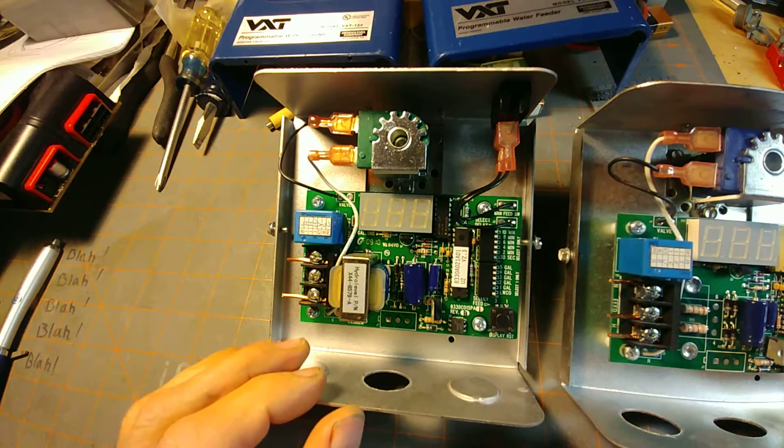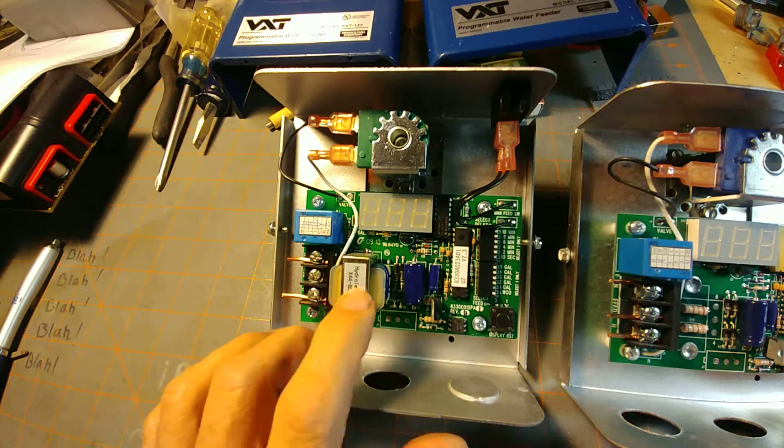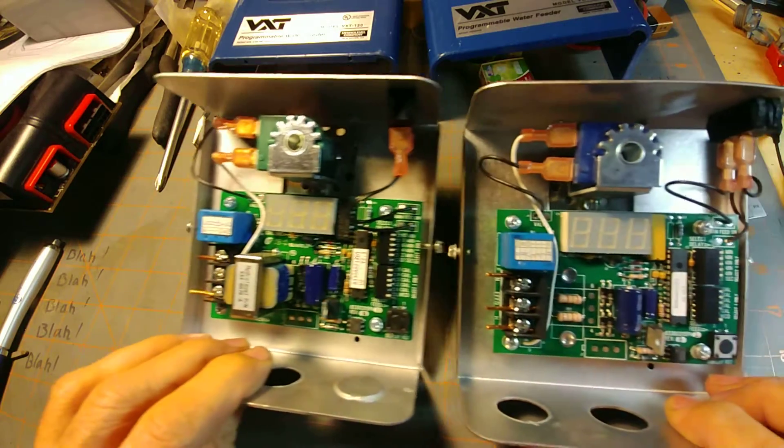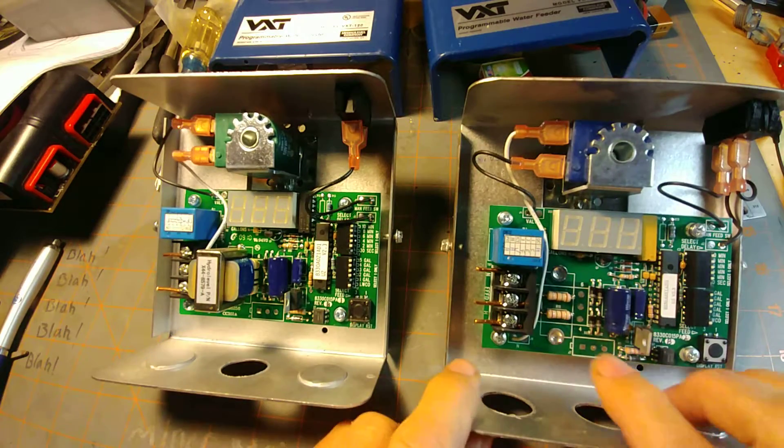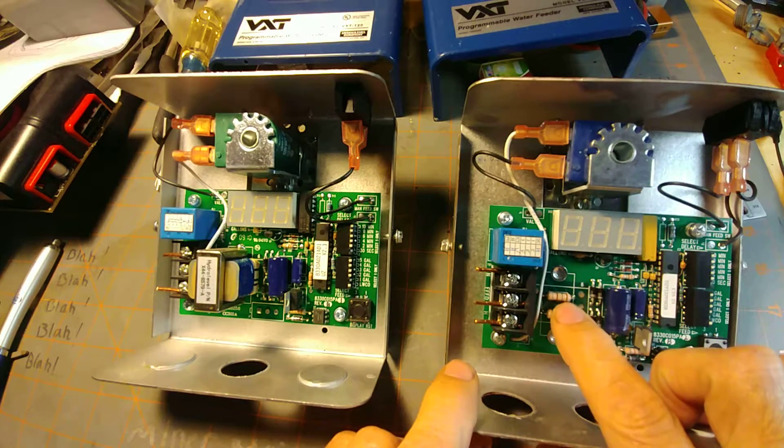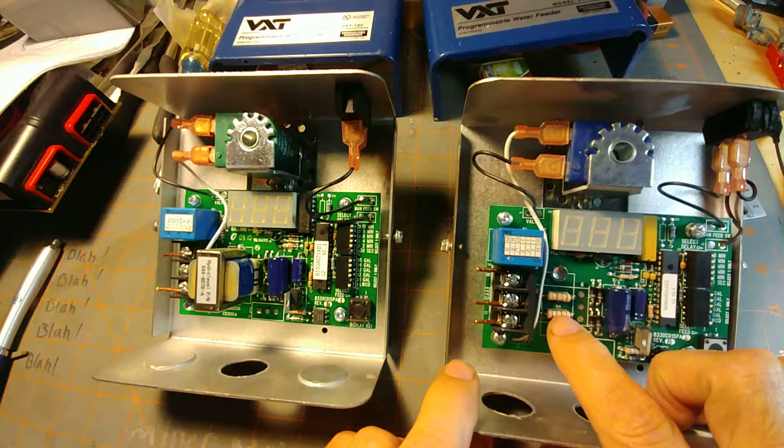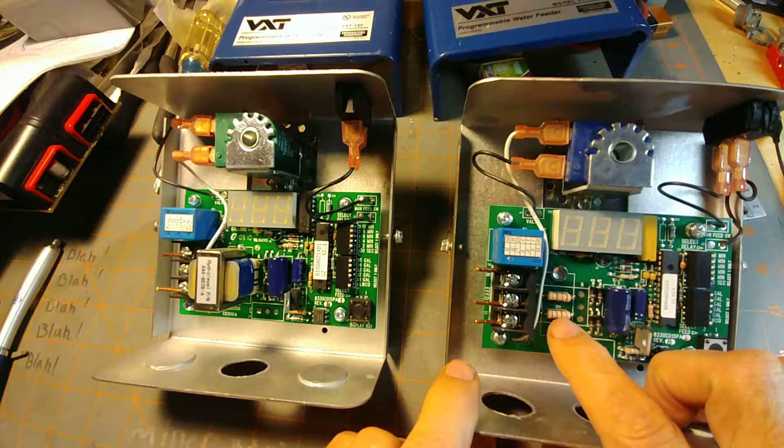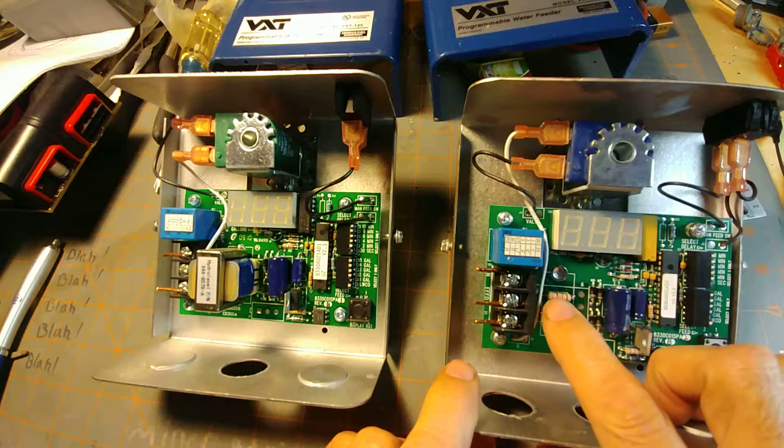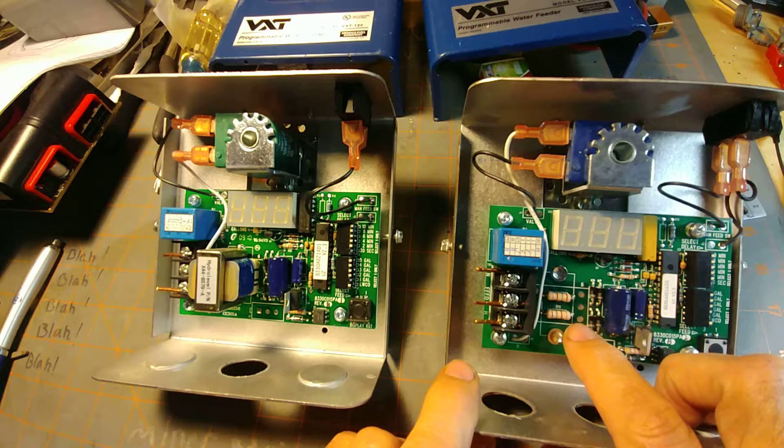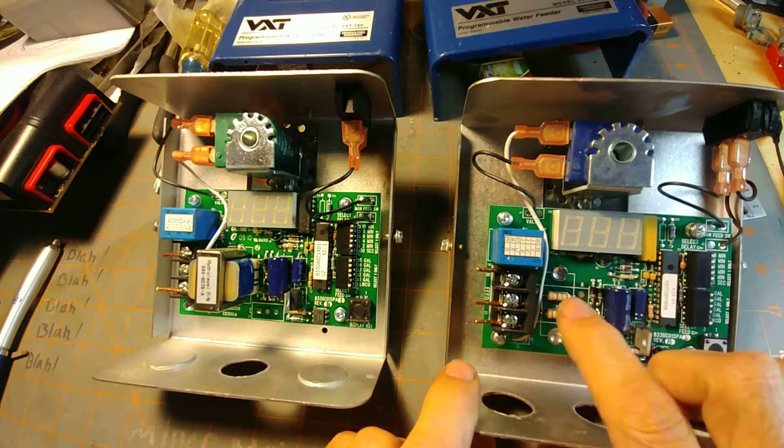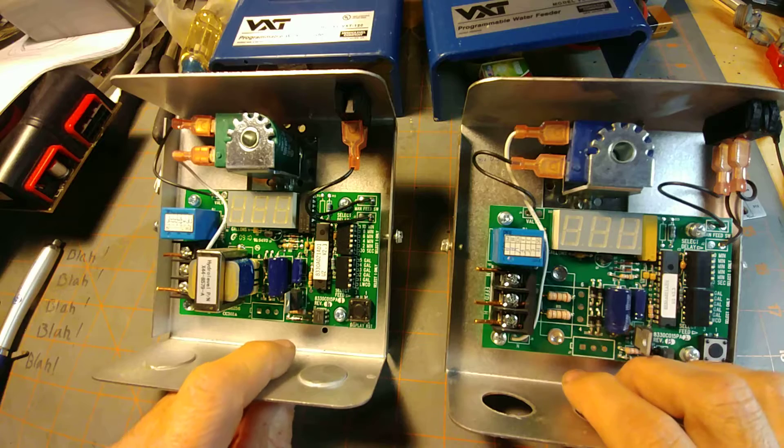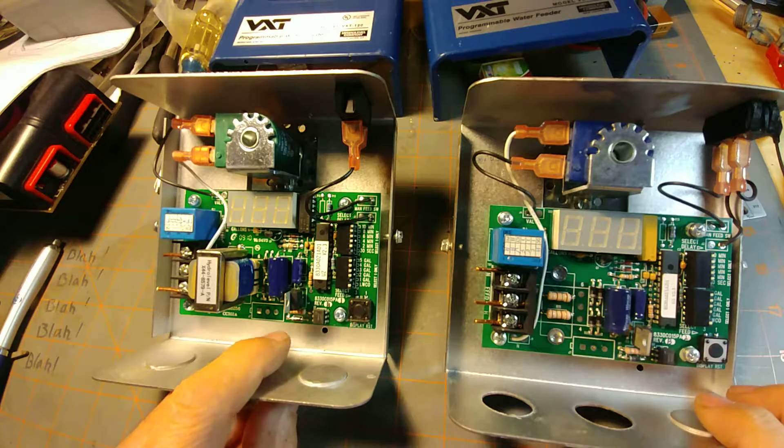With your 120-volt unit, you're going to have a transformer. In your 24-volt unit, you're going to have these two resistors here in place. These are 150-ohm resistors, about one watt, and they drop the current. These guys get a little bit warm, so be careful not to touch them.